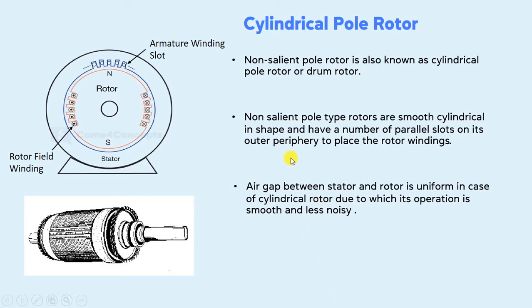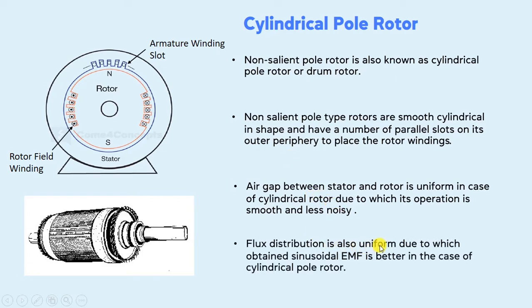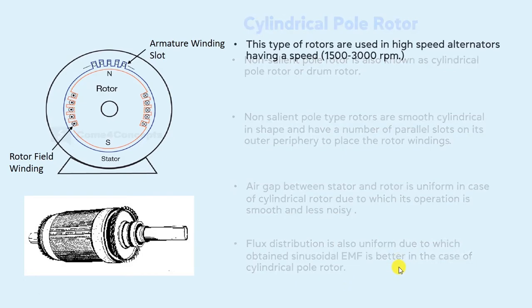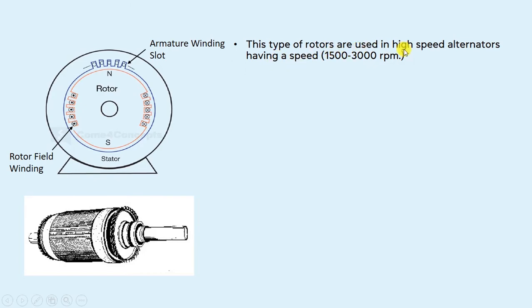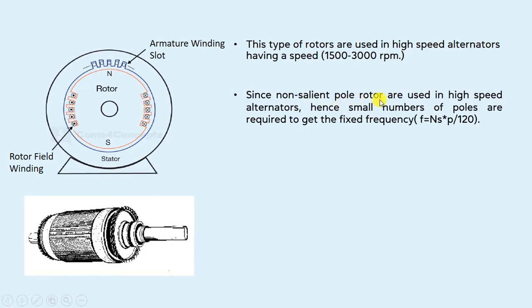Due to the uniform air gap in the cylindrical pole rotor, the flux distribution is also uniform, and as a result the sinusoidal EMF obtained is better in the case of the cylindrical pole rotor. These types of rotors are used in high-speed alternators having a speed of 1500 to 3000 RPM. Since non-salient pole rotors are used in high-speed alternators, a small number of poles are required to get the fixed frequency, as F = NP / 120 — if speed N is higher, a smaller number of poles P are required to get the desired frequency.